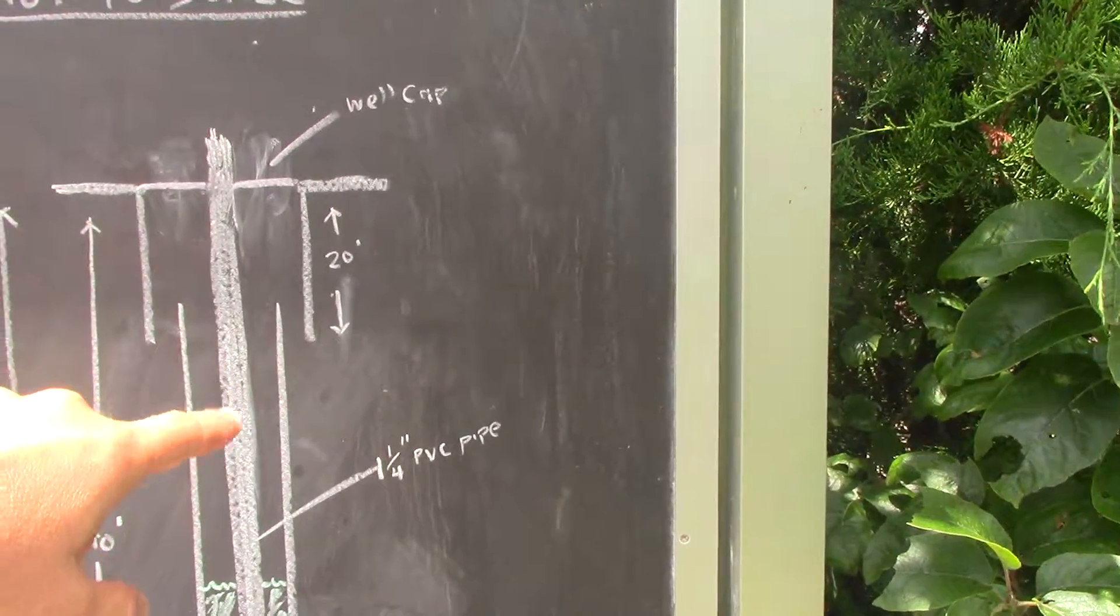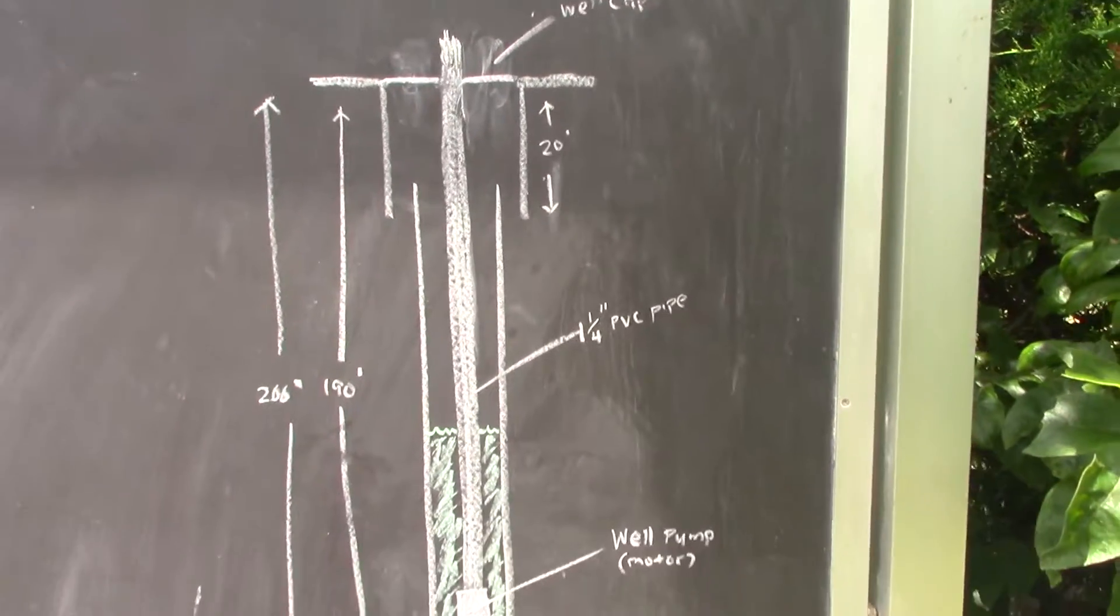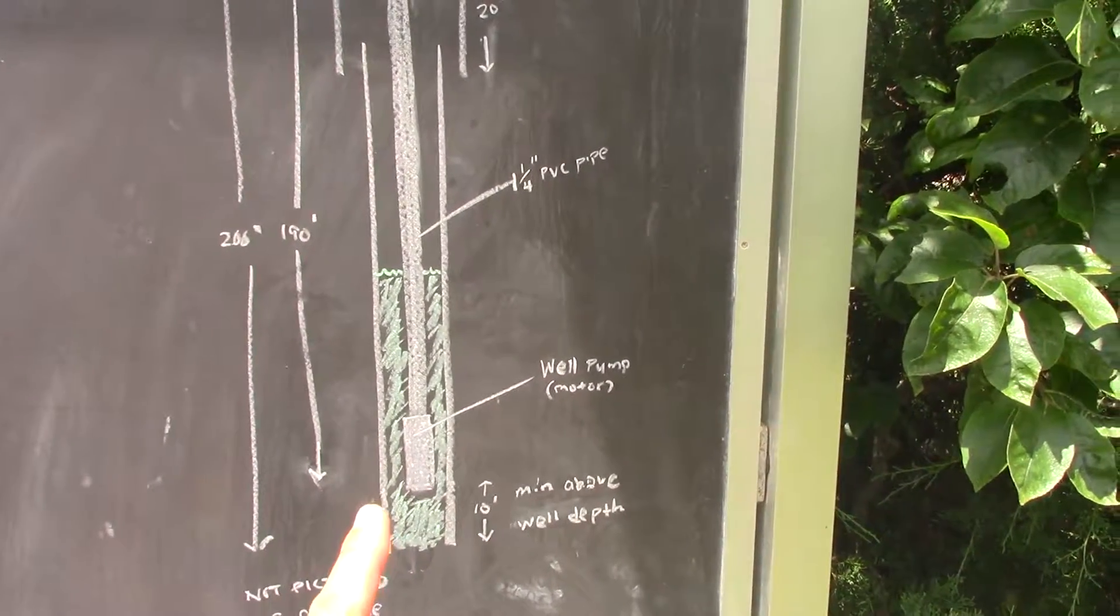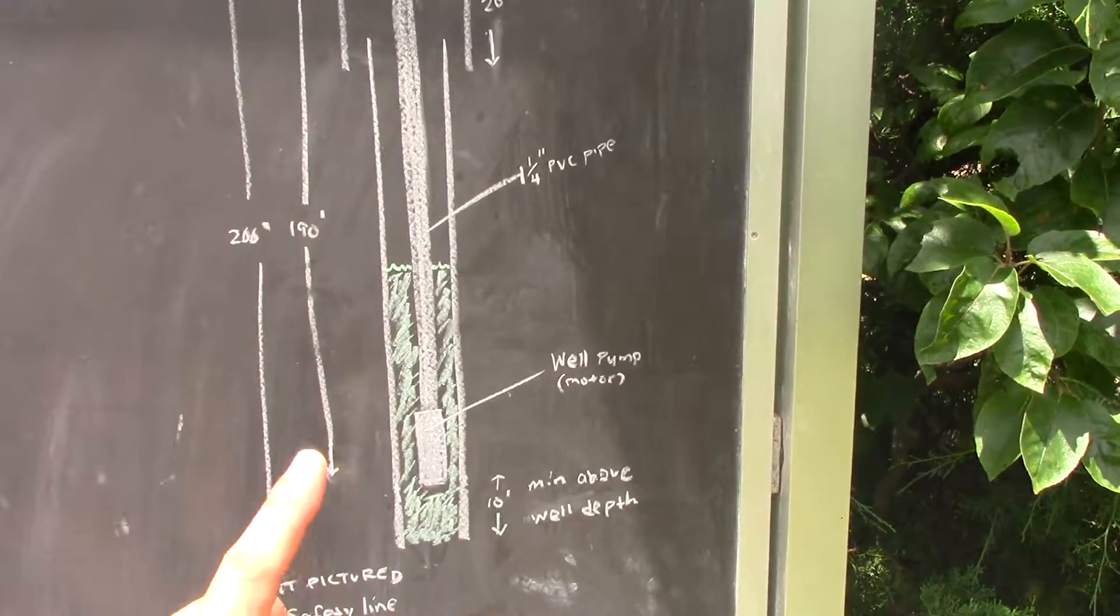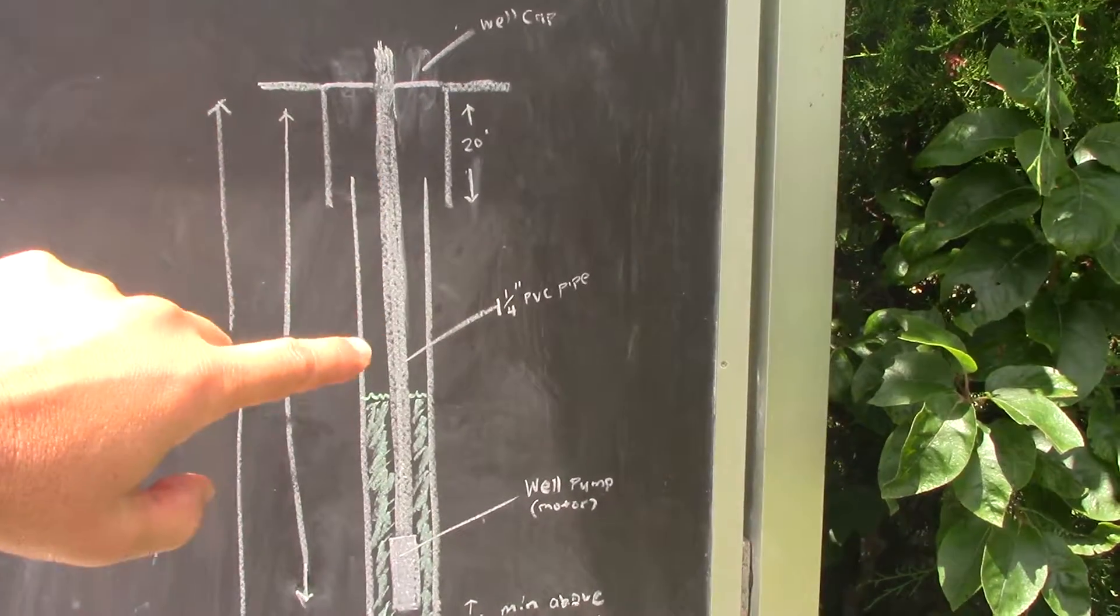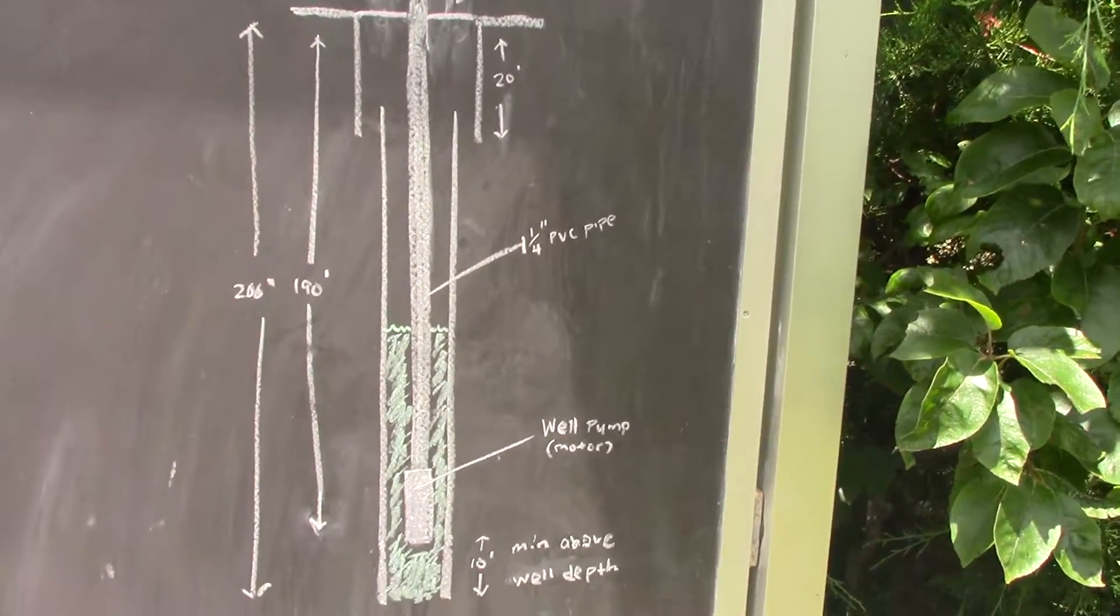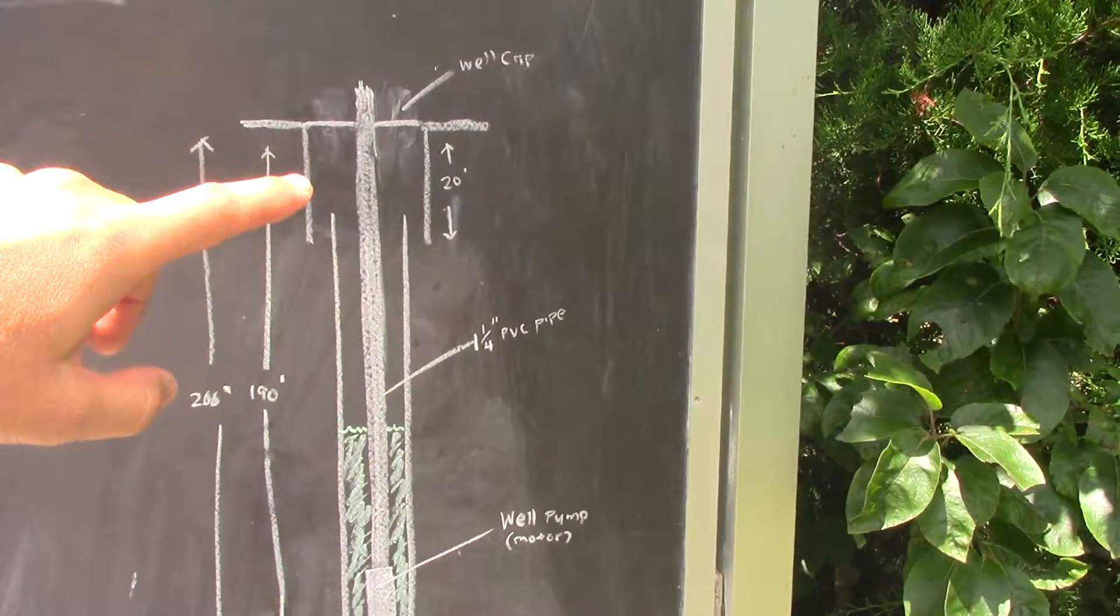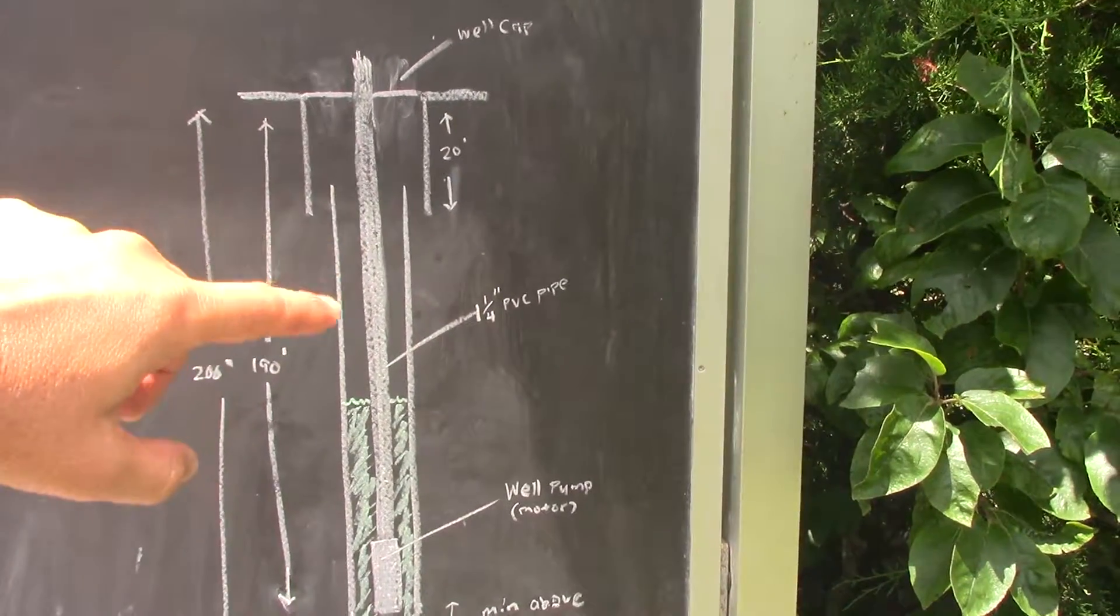The torque arrester is a nice thing to have on your well pump because the motor, as it turns, will create some degree of torque. You don't want the whole shaft spinning or any wire to get tangled up in here, so put the torque arrester somewhere in here above your water line.